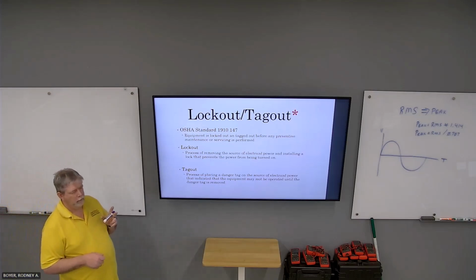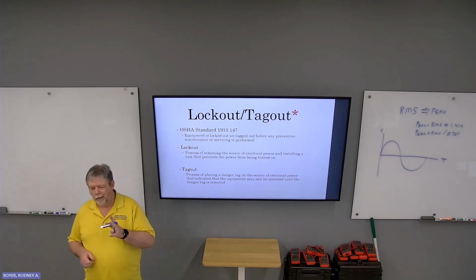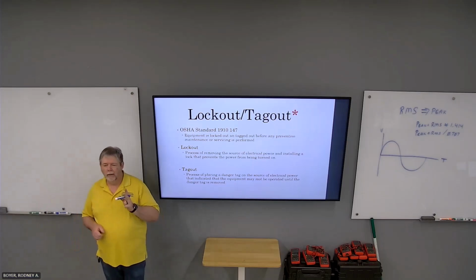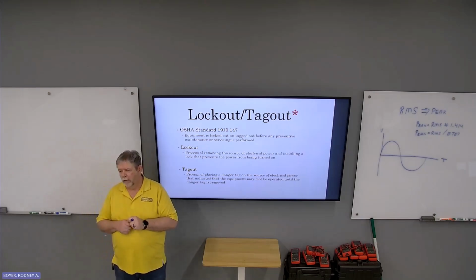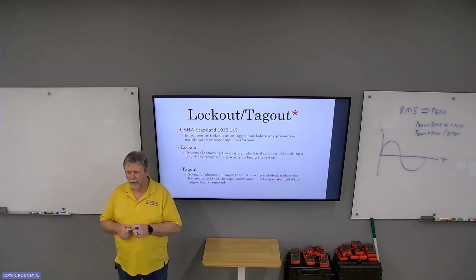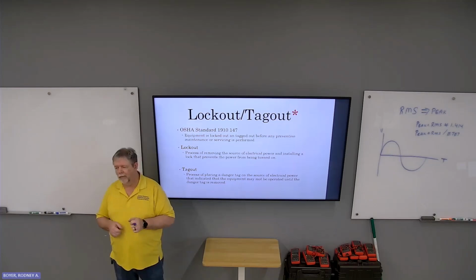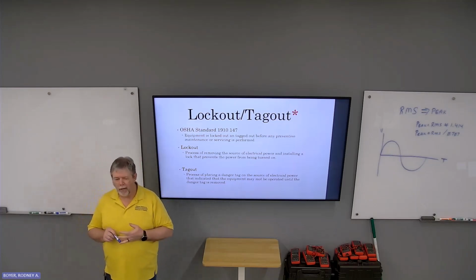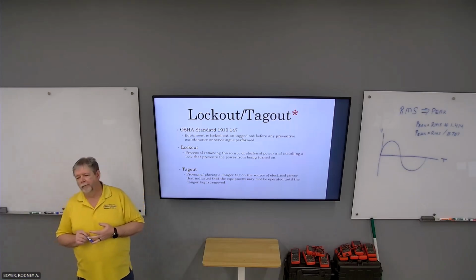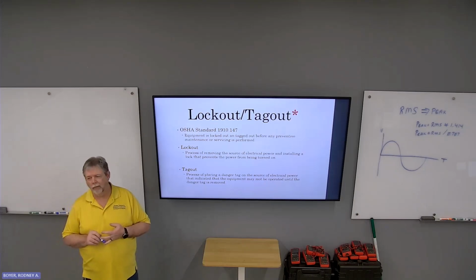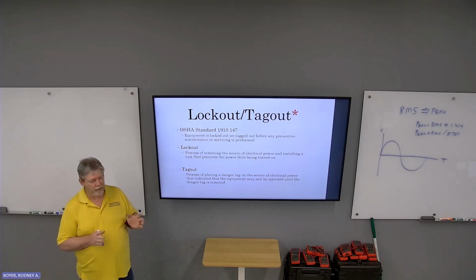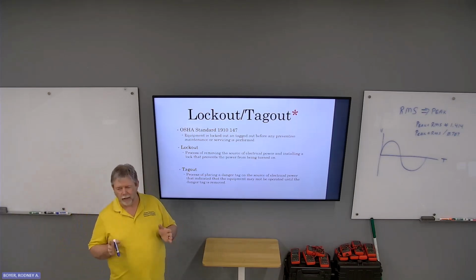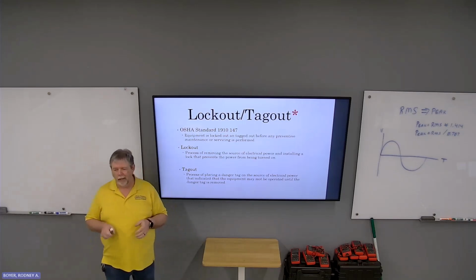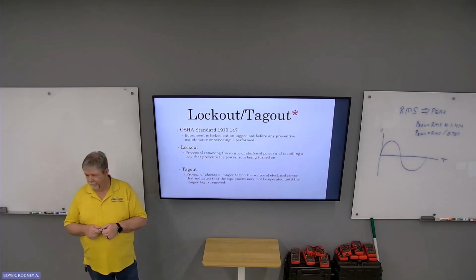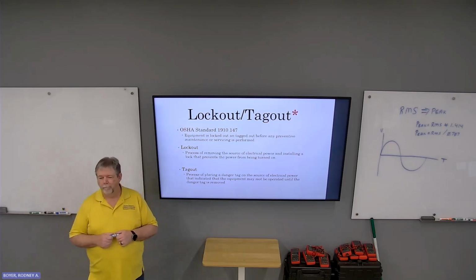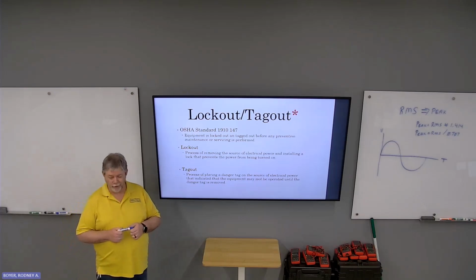It is legal in very specific circumstances to tag out only. It is 100% all the time illegal to lock out without a tag out. A lock must be accompanied by a tag. And you must lock out when it is possible. There are some very specific situations where a lockout is not physically possible. That's when a tag is okay. Is it safe? Nope. A tag does not prevent you from turning the power on. It just says, hey, you shouldn't do that.